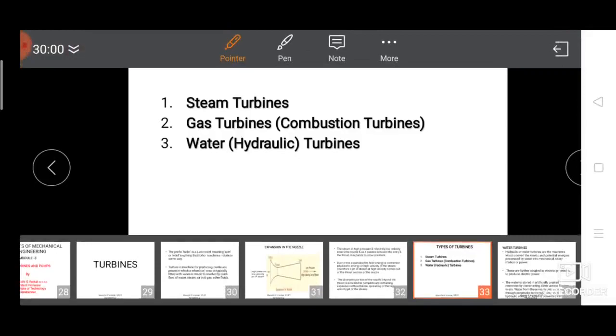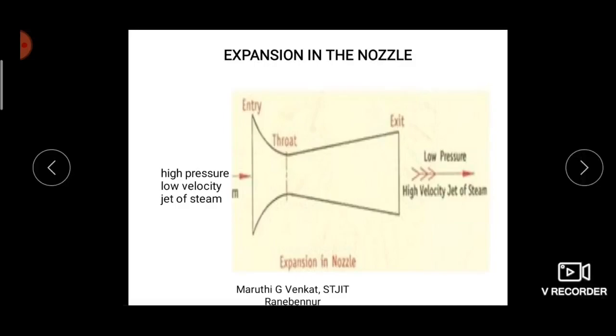Before studying all these turbines, you need to know what the nozzle effect is — that is a very important part in the case of turbines. A nozzle mainly consists of one entry and exit, and in between there is a throat. At the entry of the nozzle you supply a high pressure, low velocity jet of steam. When that steam passes through the throat, expansion takes place, so the velocity and kinetic energy of the steam increases. At the exit of the nozzle you get a low pressure, high velocity jet of steam.